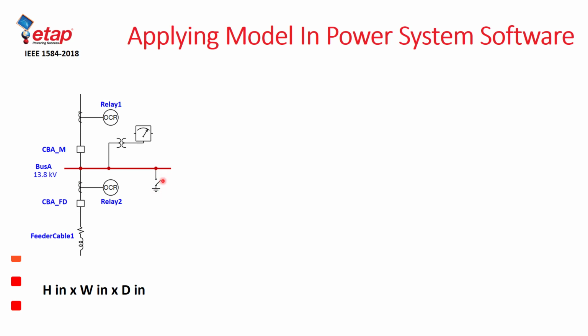in different enclosures. Previous versions of the standard only allowed us to select the orientation, either VOA or VCB. And of course, we are talking about enclosed equipment, so this will be considered as VCB. And furthermore, just to specify the gap and the correct X factor, and that would be all the information required. All of these enclosures would then be modeled with a uniform size, without regard to the potential variations in energy which could come from the different enclosure sizes.